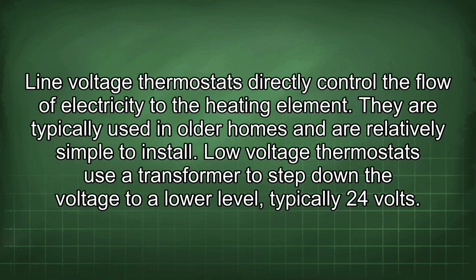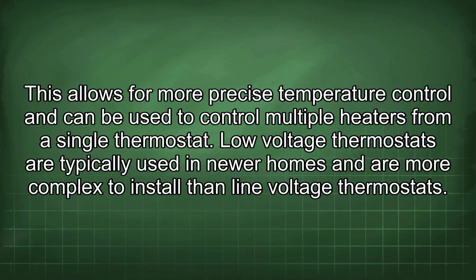Low voltage thermostats use a transformer to step down the voltage to a lower level, typically 24 volts. This allows for more precise temperature control and can be used to control multiple heaters from a single thermostat. Low voltage thermostats are typically used in newer homes and are more complex to install than line voltage thermostats.